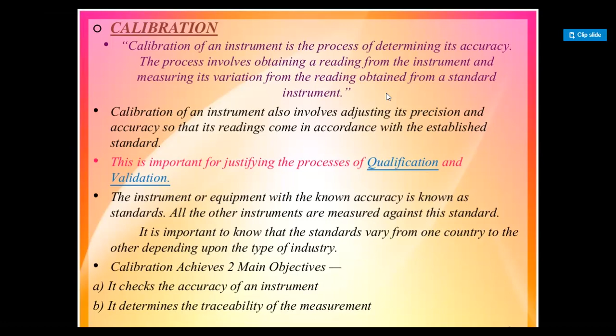Calibration of an instrument is the process of determining its accuracy. The process involves obtaining a reading from the instrument and measuring its variation from the reading obtained from a standard instrument. Calibration of an instrument also involves adjusting its precision and accuracy so that its readings come in accordance with the established standard. This is important for justifying the process of qualification and validation. Qualification and validation we will discuss later, but first of all, we will discuss calibration.